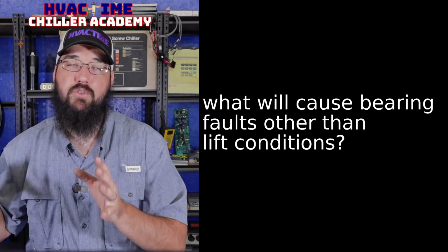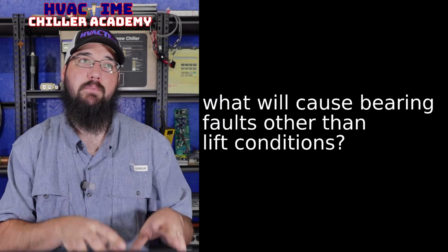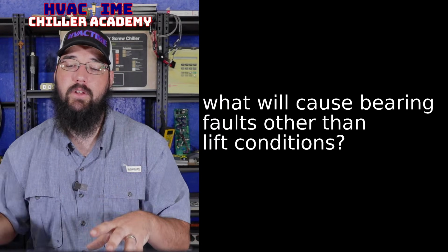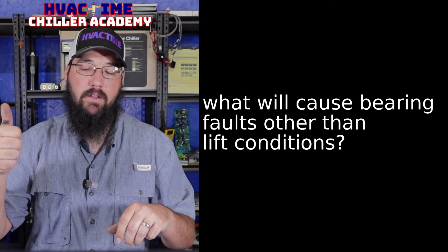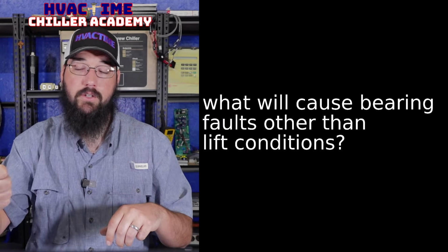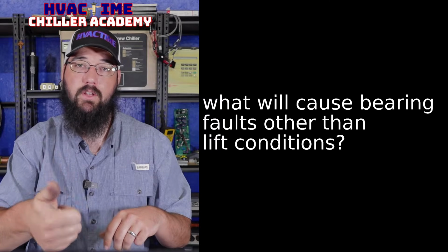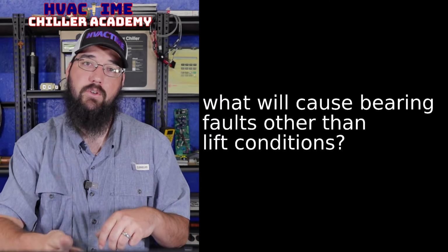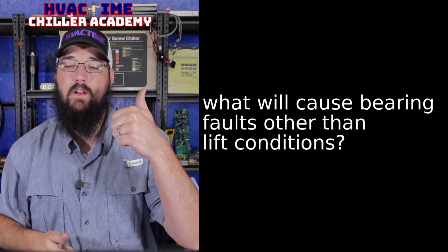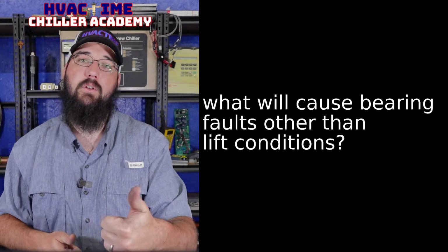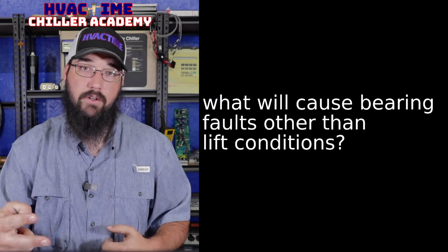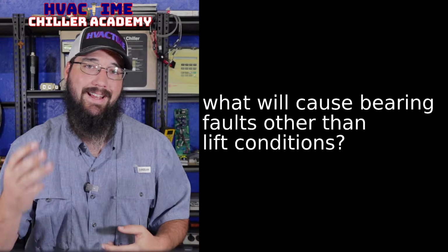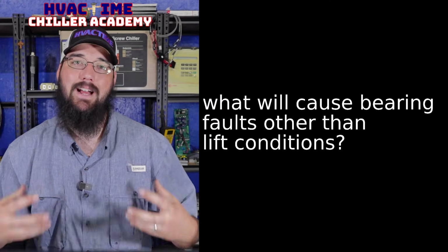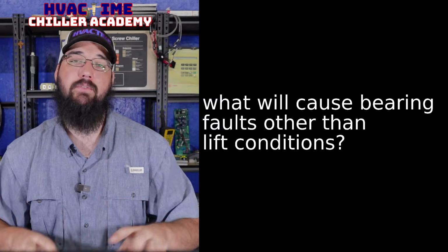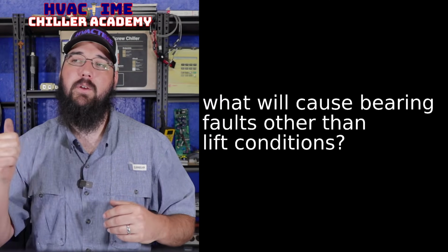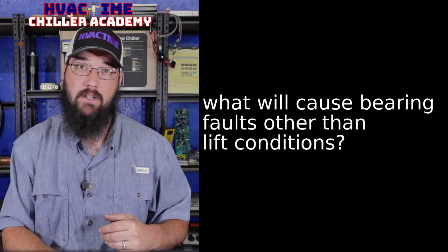Having verified the bearing calibration is part of the process. So lift could be one issue. Specifically, when we say lift, we're discussing stall and surge. So stalling and surging could be one issue. We could have a bearing or a sensor issue. We could have an inverter issue, a demag issue, or a bearing calibration issue. Those are the main high-level points that I'm going to be trying to verify in the process. The bearing calibration does not lead to a new compressor.